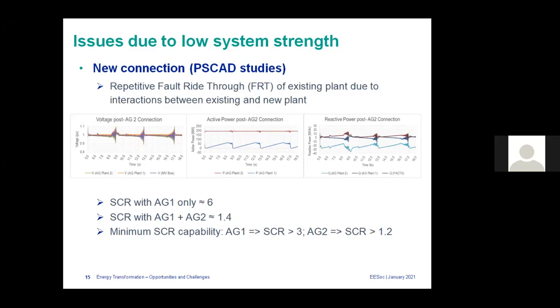But the second plant, the wind farm, is a type 3, DFIG, doubly fed induction machine kind of generation. What they say is they can operate in a stable way if the SCR is more than 1.2. Wind farms are quite good, especially type 3 wind farms, those DFIG machines, because they are not really purely inverter based. I think you might have studied all these. Type 4 has an inverter interface, a completely power electronic interface, but type 3 has a partial interface, so they can operate in low system strength areas much better than type 4s. So these wind turbine generators said they can operate if the SCR is more than 1.2.